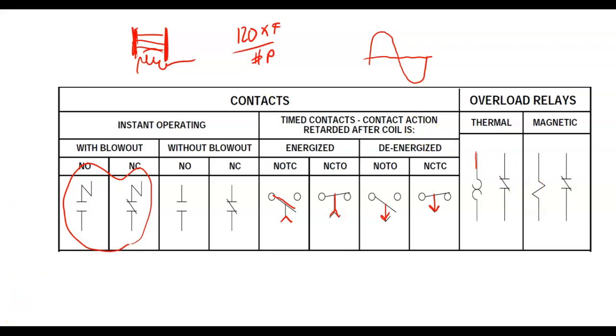The problem with motors is that they require a lot of starting current. But once they're up to speed, the current drops back. In fact, motors will have a code on there. They don't tell you what the starting current is, but there's a code on there and you can look it up on the chart and it will tell you the multiplier. So if you look at the amp rating on a motor, that is not the start current, that is the run current. It's the current at rated horsepower and rated voltage.